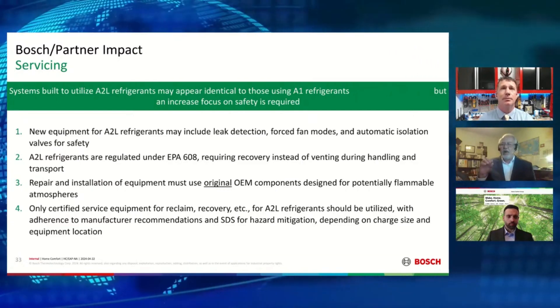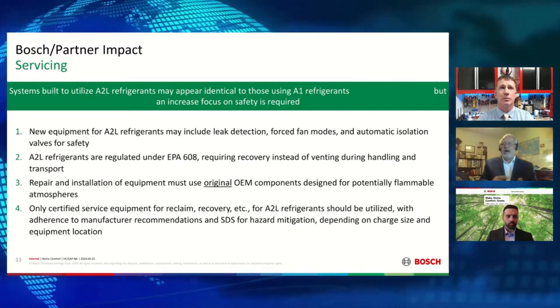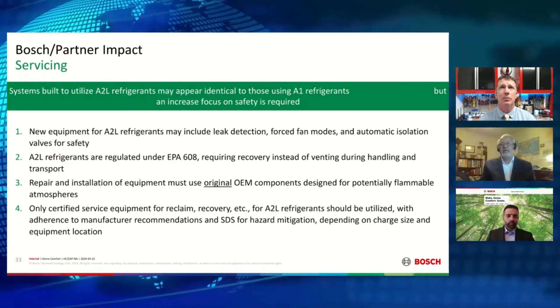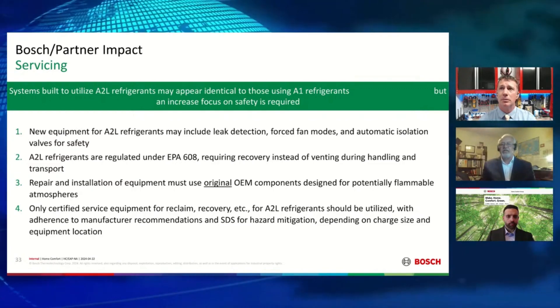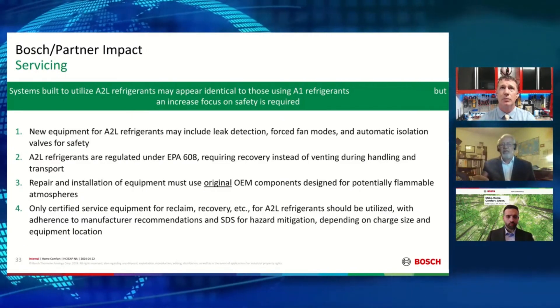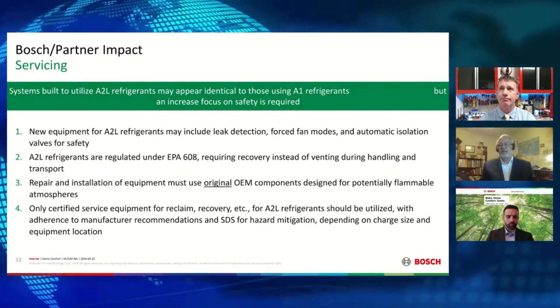All new equipment for A2L refrigerants may include leak detection, forced fan modes, and automatic isolation valves. A2L refrigerants are regulated under EPA 608, which requires recovery instead of venting during handling and transportation. For repair and installation, you must always use original OEM components designed for potentially flammable atmospheres, and only certified service equipment — such as reclamation and recovery equipment for A2L refrigerants — should be utilized. Adherence to manufacturer recommendations and safety data sheets for hazard mitigation is dependent on charge size and equipment location.